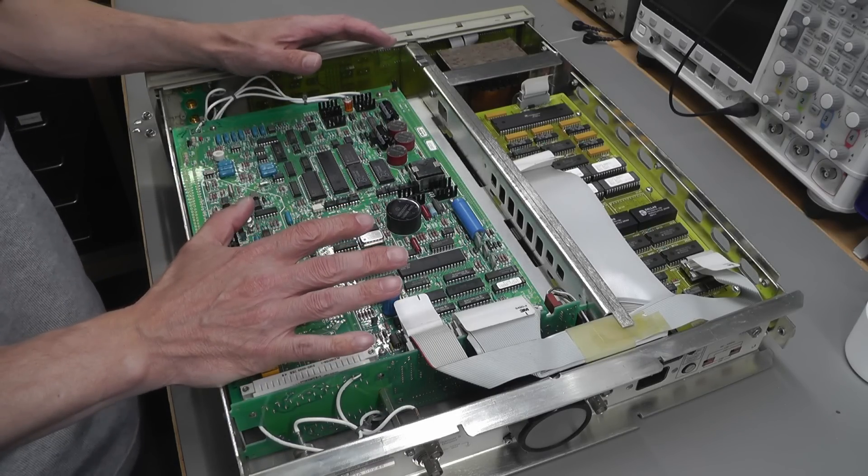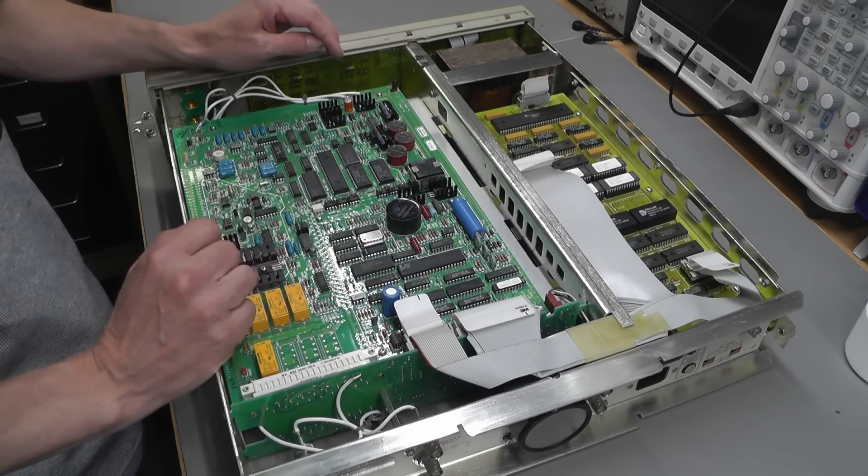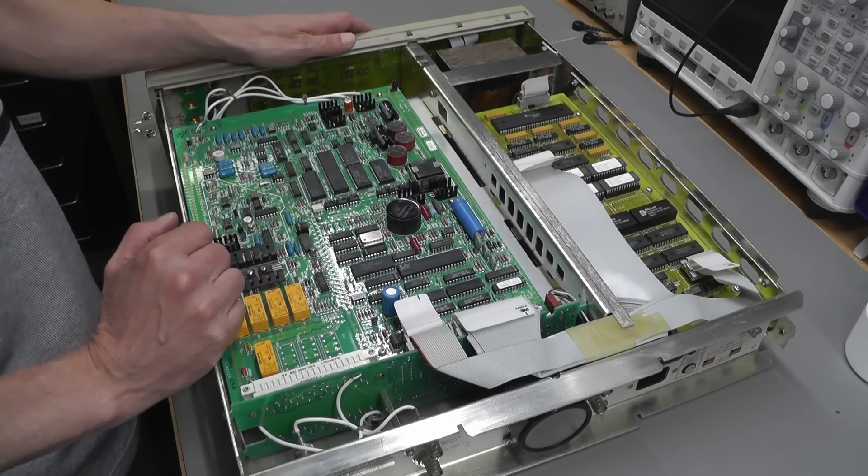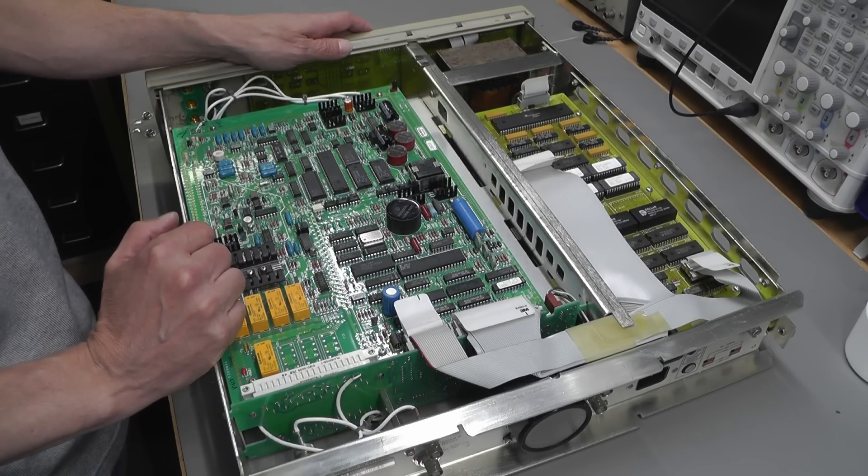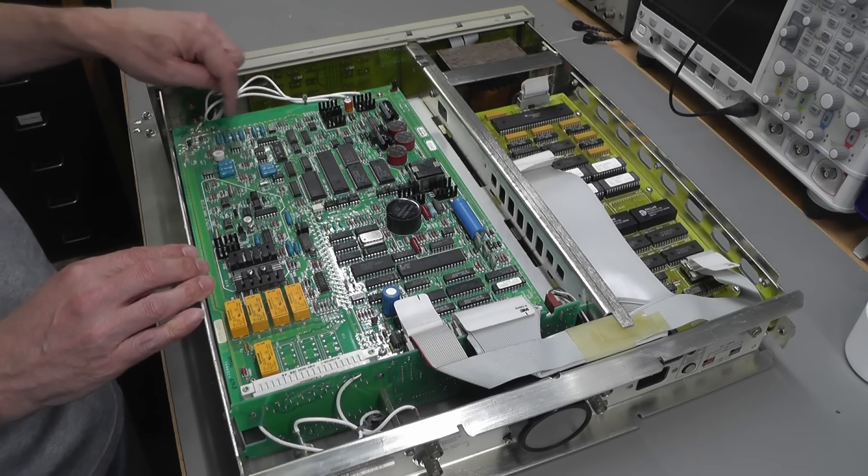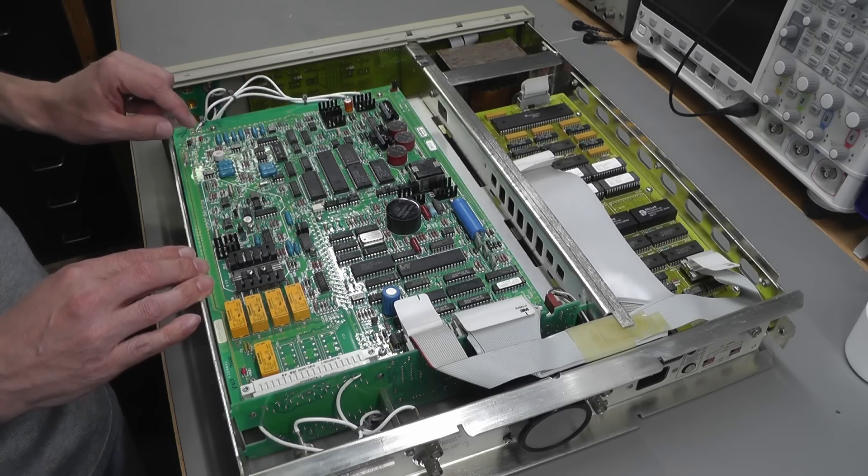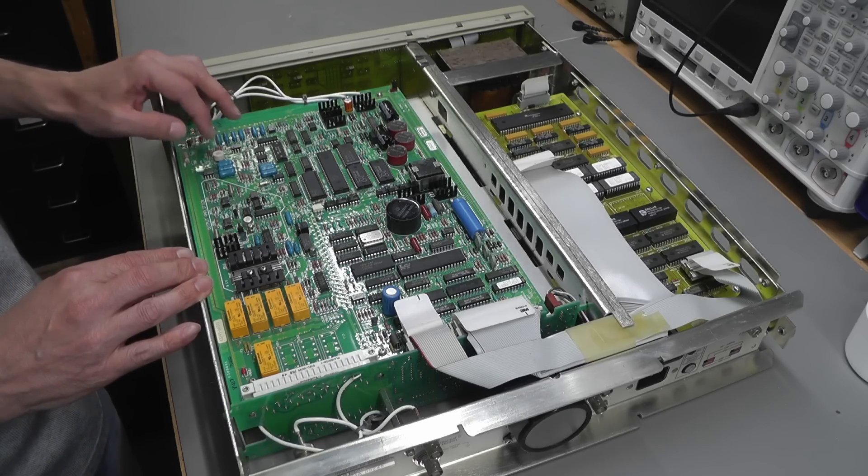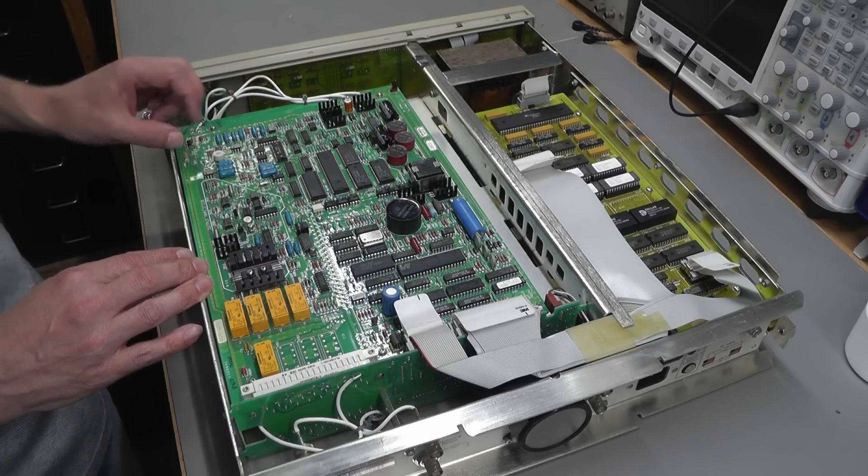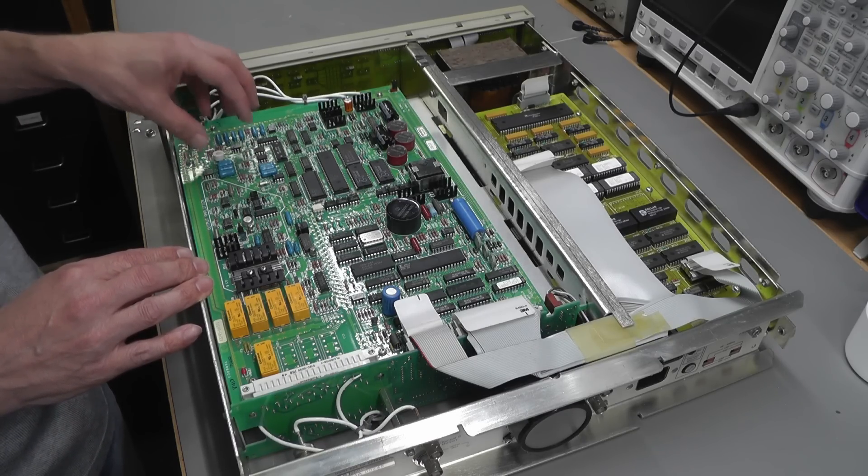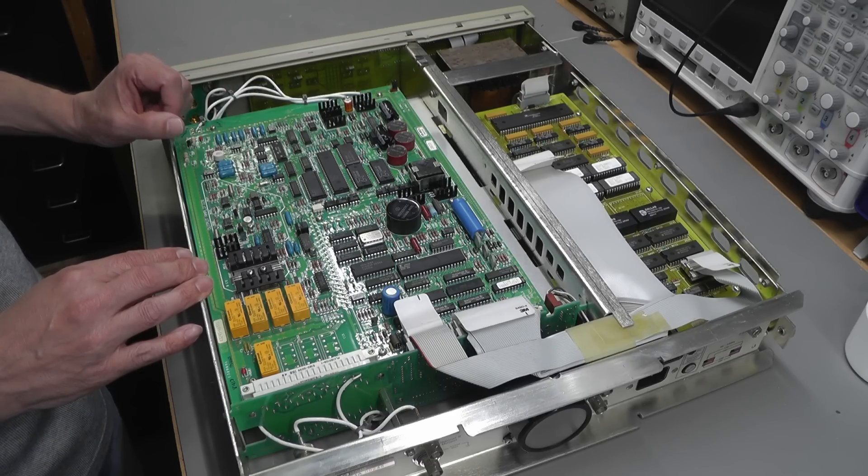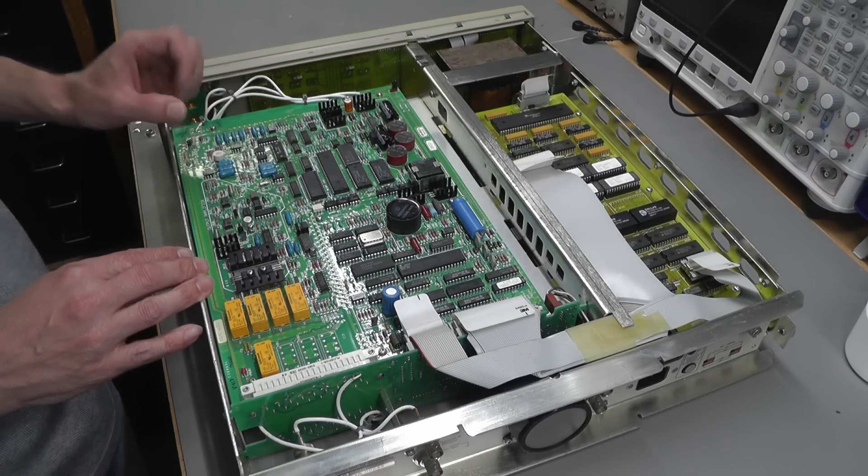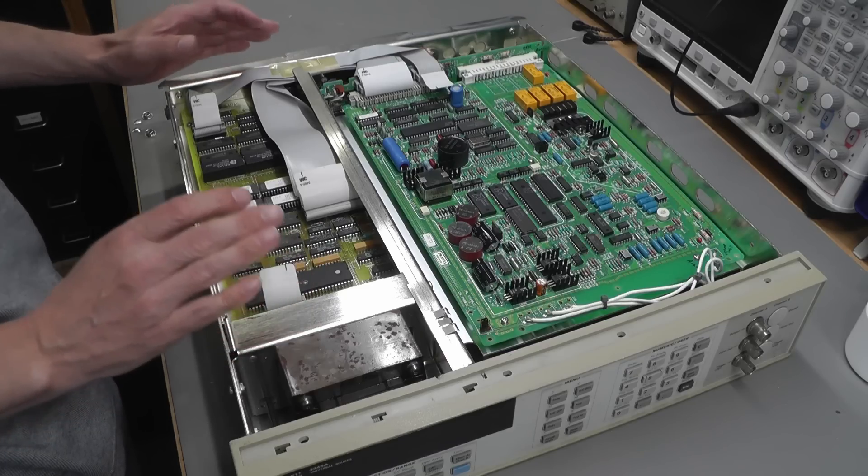Turning it over, this is the main A1 board, the in-guard source PC assembly. This is the main analog board basically that takes its instructions from the CPU board and outputs onto the front panel. There are some electrolytic capacitors I will be replacing—recapping the board. And over here is the main Vref circuit consisting of an LM399 and associated op-amps, etc. I do want to make some modifications over here, hopefully to try to improve the 3245A.